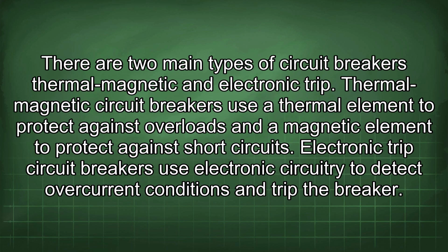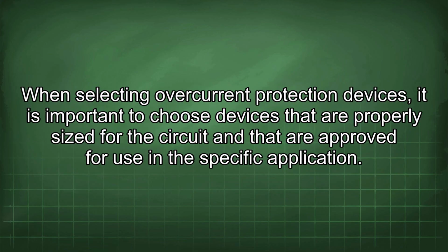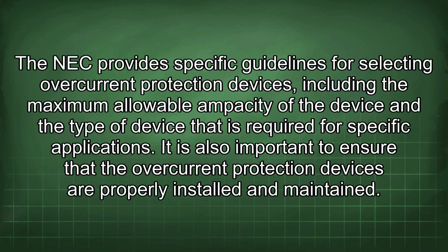There are two main types of circuit breakers: thermal magnetic and electronic trip. Thermal magnetic circuit breakers use a thermal element to protect against overloads and a magnetic element to protect against short circuits. Electronic trip circuit breakers use electronic circuitry to detect overcurrent conditions and trip the breaker. When selecting overcurrent protection devices, it is important to choose devices that are properly sized for the circuit and that are approved for use in the specific application. The NEC provides specific guidelines for selecting overcurrent protection devices, including the maximum allowable ampacity of the device and the type of device that is required for specific applications.